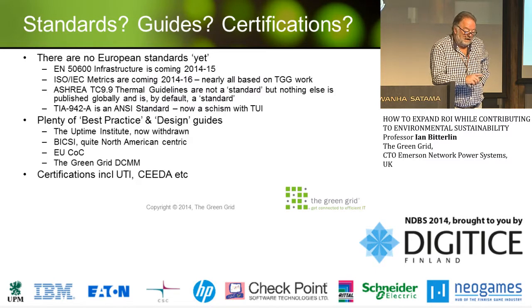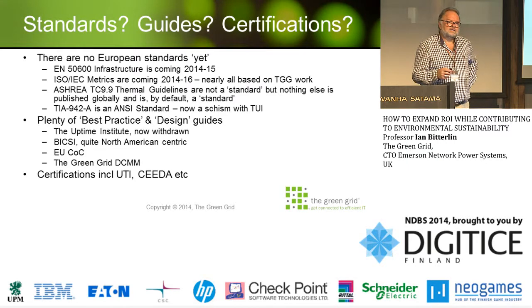If you apply ASHRAE TC 9.9 thermal guidelines, especially going from the recommended into the allowable range, you can build a data centre anywhere in Europe with the same 100% free cooling and no compressors. So my advice to anyone in Scandinavia: it's a good thing to talk about, but don't hang your hat on it—the time has passed for that to be a real unique selling point.